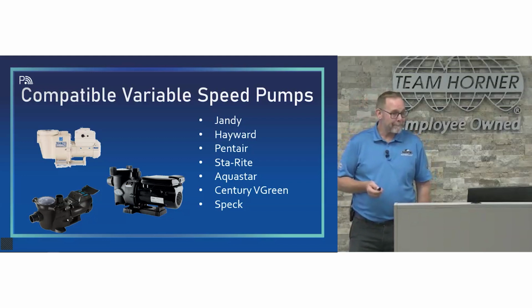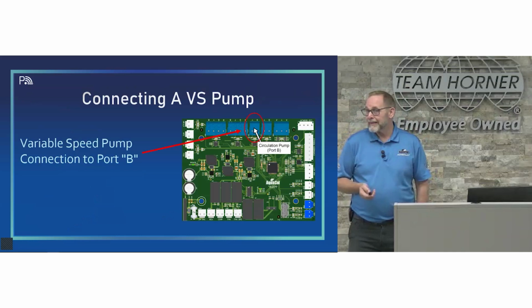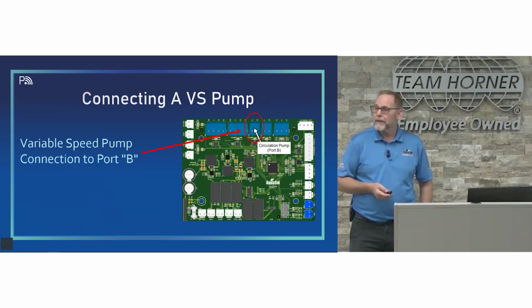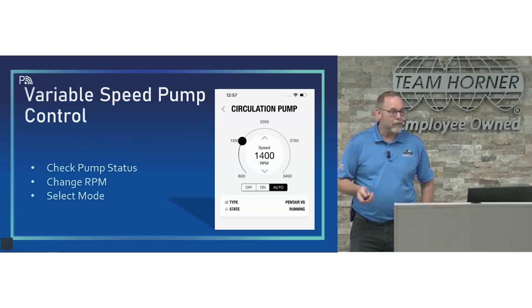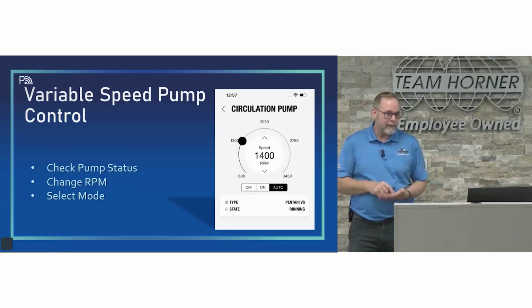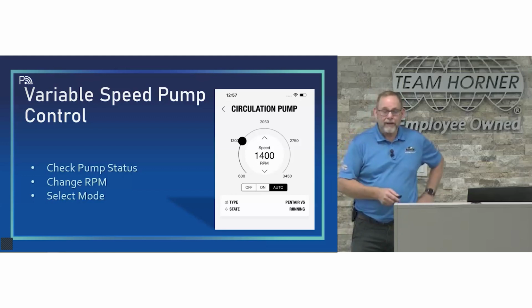It's as easy as connecting the communication cable for the pump right to port B on the heat pump. And then once we're controlling it, we've got full variable speed pump control. I like using this feature if I'm setting up a waterfall or trying to determine my perfect flow rate for the pool. You can sit there and change it in 50 RPM increments and tweak it, find out exactly the right pump speed.